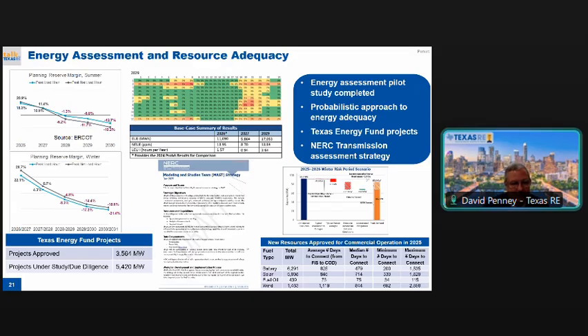Based on the probabilities, you can calculate expected unserved energy or loss of load hours over the course of the year, and the big thing it shows is where your high risk hours are. If you look at the map, from a winter perspective our highest risk hours are 6, 7, and 8 in the morning, and in summertime it's 8, 9, 10, and 11 at night. That bears out with what we're seeing in real time given how the grid is operated today.